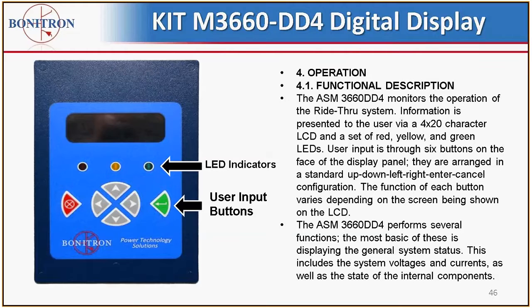Functionally, it monitors the ride-through system completely. You're going to have LED indicators that pretty much correspond to the basic indicators, and they will give you unit state of health. And you're going to have a ride-through ready, ride-through active, and a fault indication. Also, there are push buttons that will take you through the different menus. As I said, this is just indicators and basic connectivity. In the next presentation, we're going to be going through the different displays of the DD4.